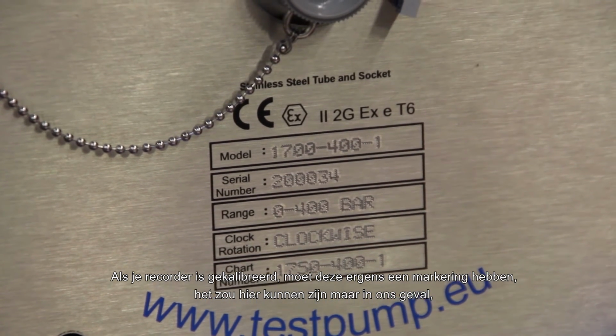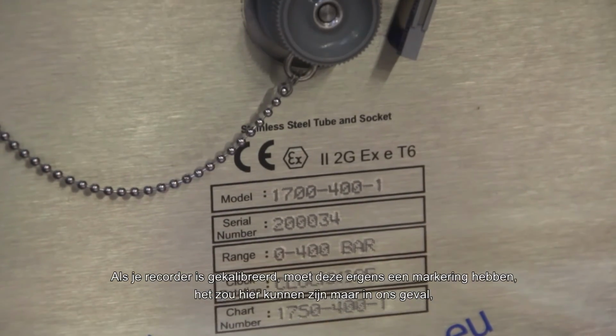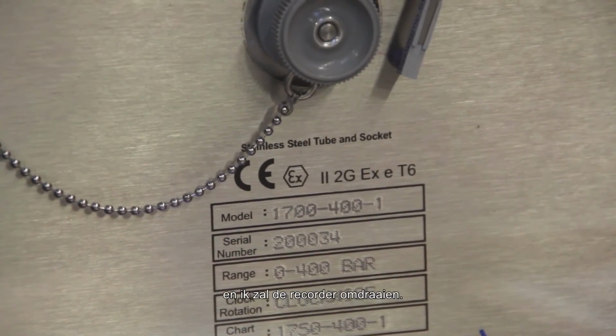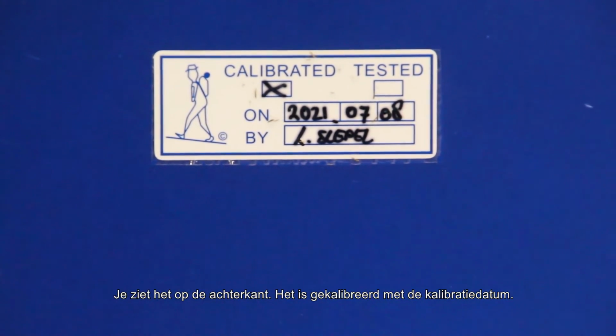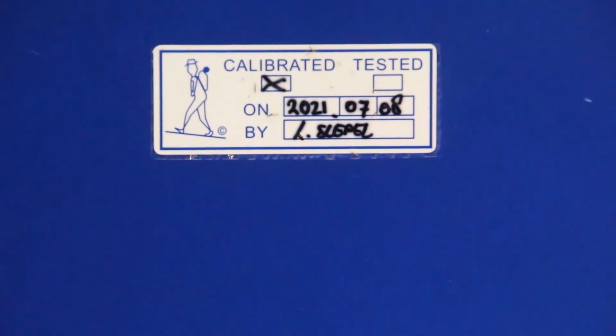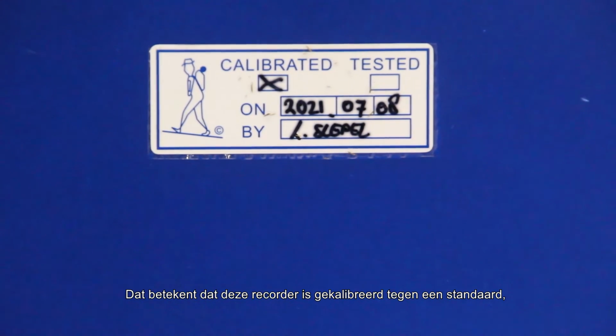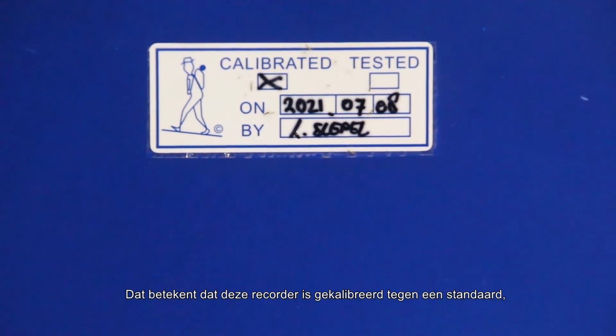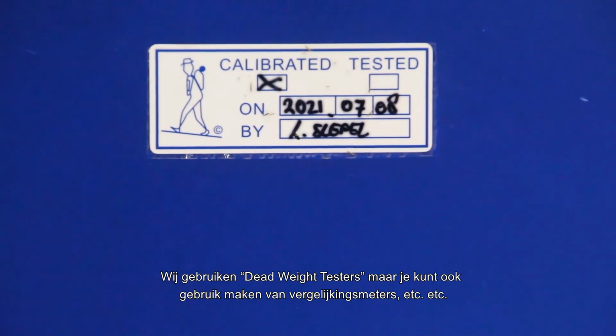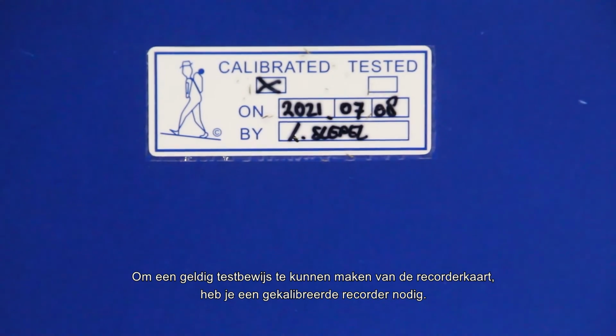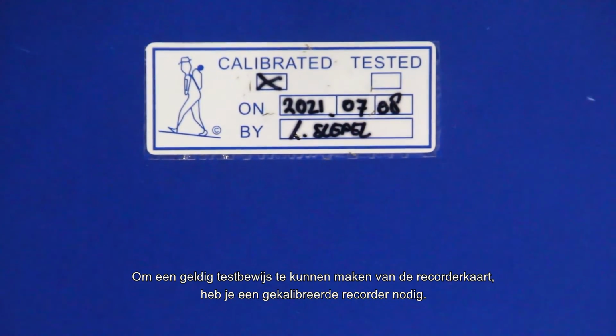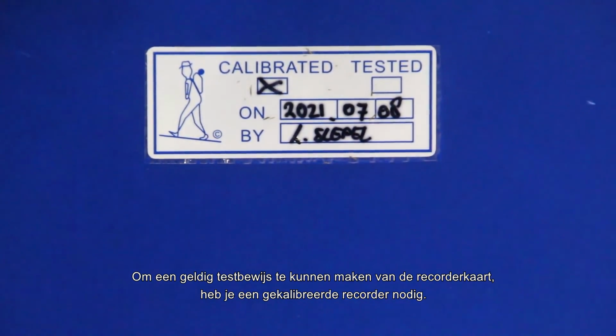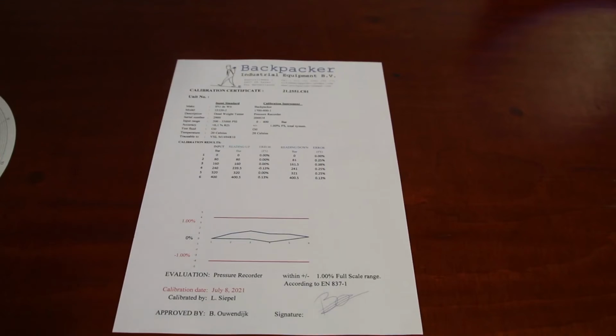It could be here. In our case, and I'll turn the recorder over, you see it in the back, it's calibrated with the calibration date. That means that this recorder has been calibrated against a standard. We use deadweight testers, you can also use comparison gauges, etc. But to create valid test evidence with your recorder chart, you need a calibrated recorder.